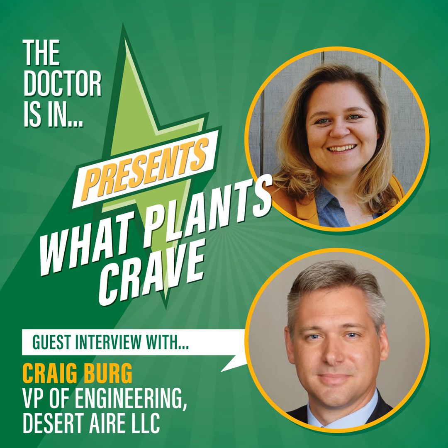Interesting. So I want to make sure that I'm clear, because maybe I've been thinking about it incorrectly. So hot gas reheat is taking hot gas from the compressor. It's not taking the hot gas from the evaporator. Part of me always thought, like, the evaporator is absorbing this energy, and then we're diverting it, rather than going through the rest of the circuit, we divert some of that expanded, that hot refrigerant, to the hot gas reheat coil. But it's not coming from the evaporator coil. It's coming directly from the compressor.